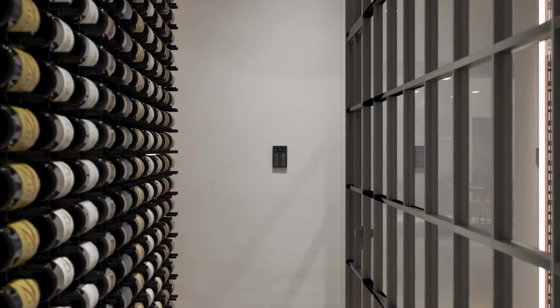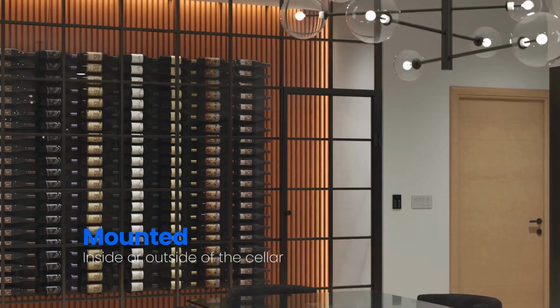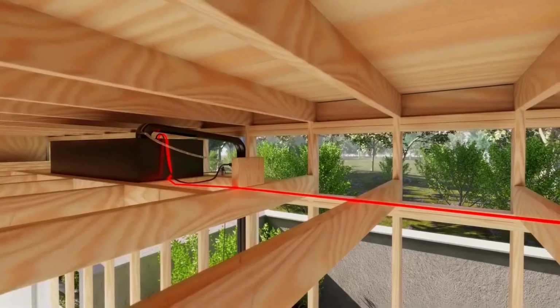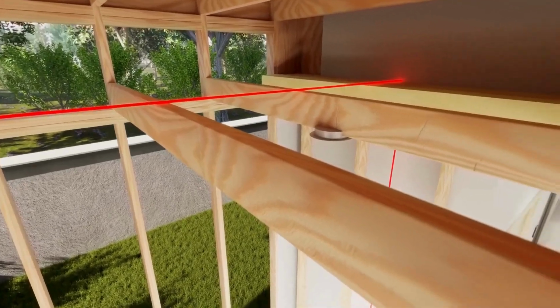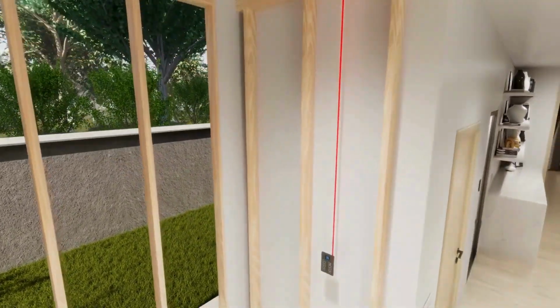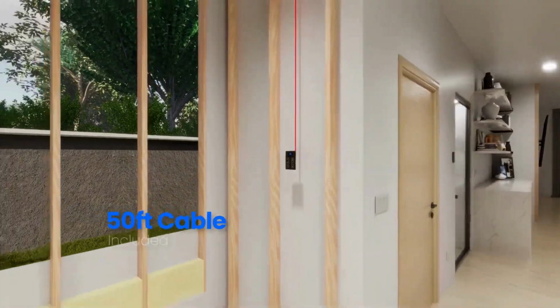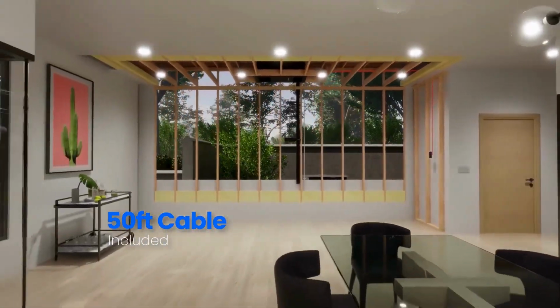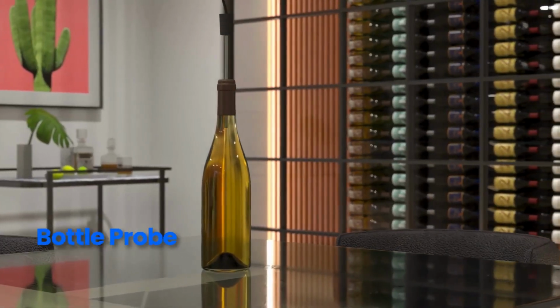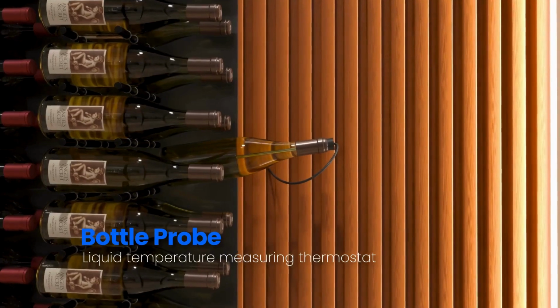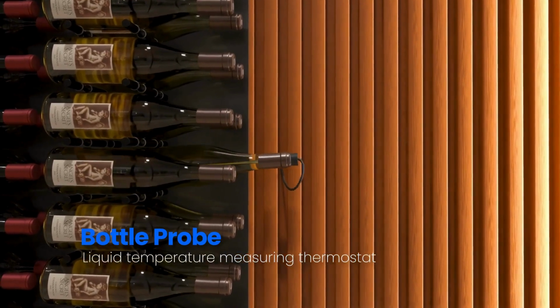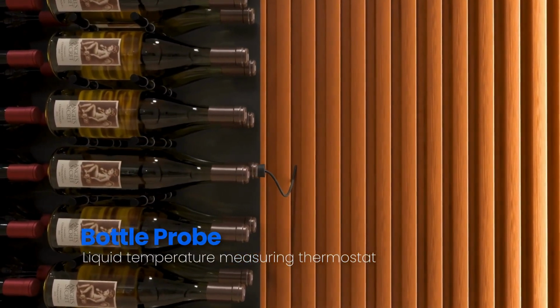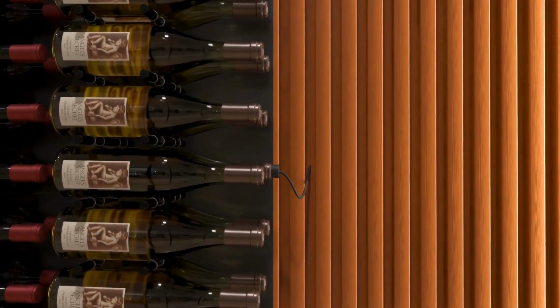The controller display can be wall mounted either inside or outside of the cellar. Route the display cable from the evaporator unit to the desired keypad location. A 50-foot cable is included with the system. WhisperKOOL series cooling units come equipped with a liquid temperature measuring thermostat. The bottle probe for the thermostat must be mounted inside the cellar in order to read the proper temperature.